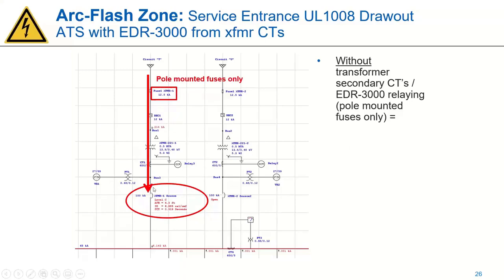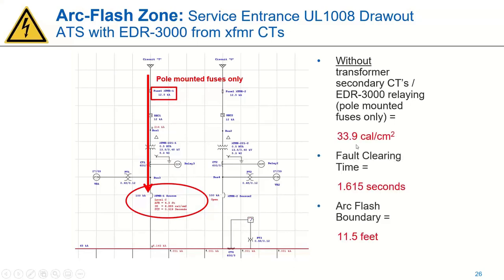If I was going to wait for that pole mounted fuse to go off in order to protect my zone, again, my zone being a really big hazard zone, pretty much anywhere between that pole mount fuse and my LV main, I'm going to result in a 33.9 calorie per centimeter squared arc flash energy. Now you might say this is below 40. This is accessible. This is a customer that had a strong preference for the gloves and face shield.